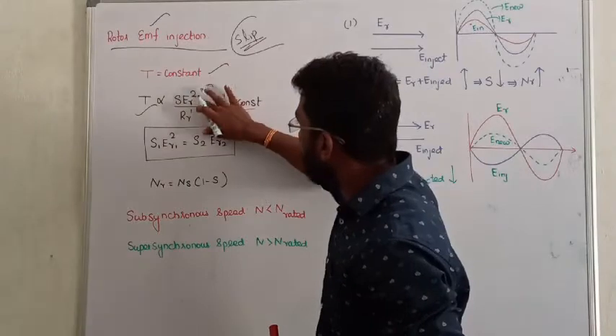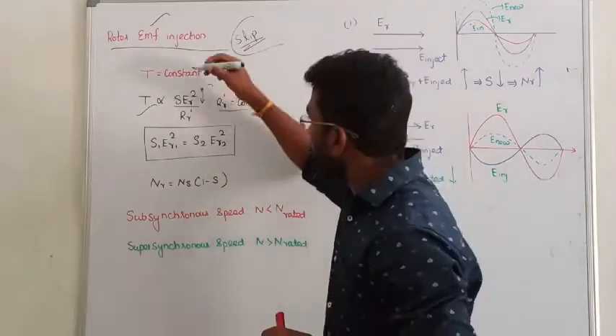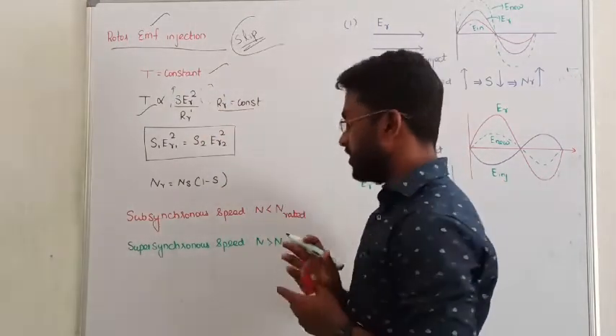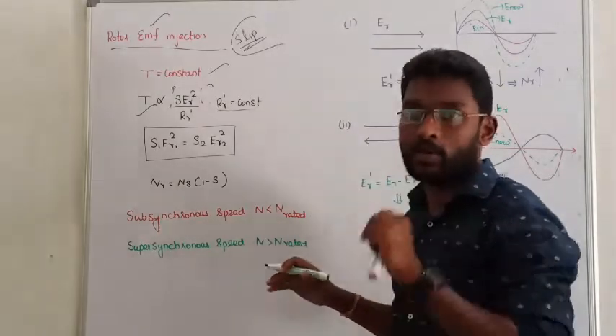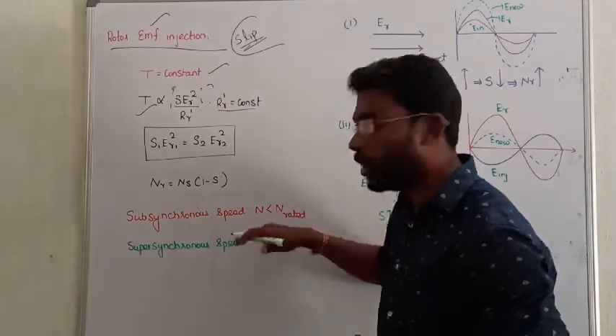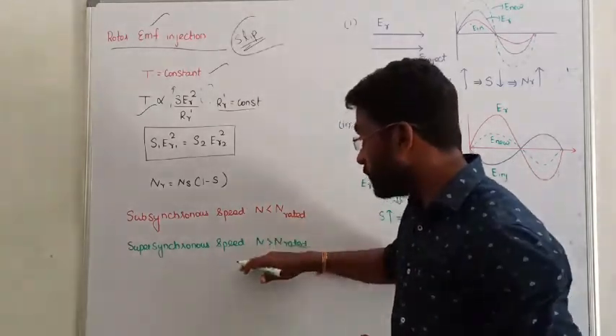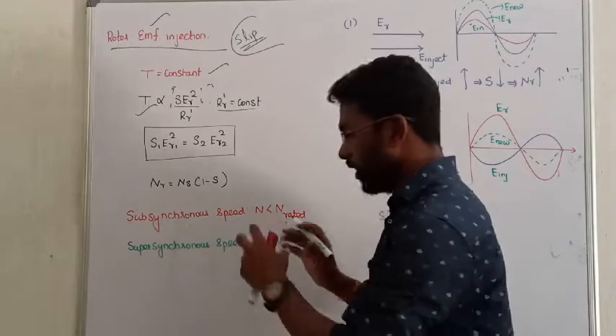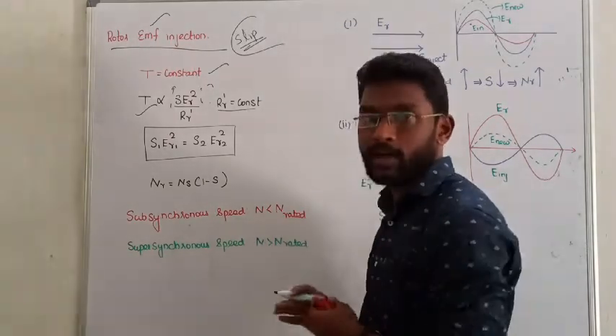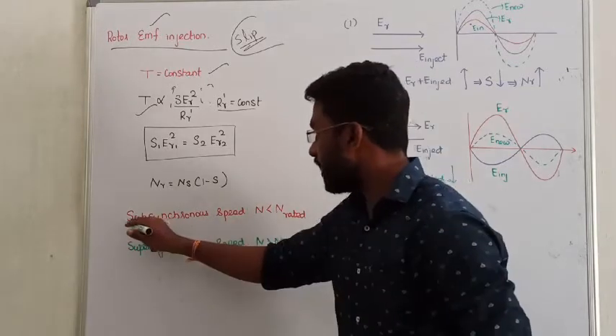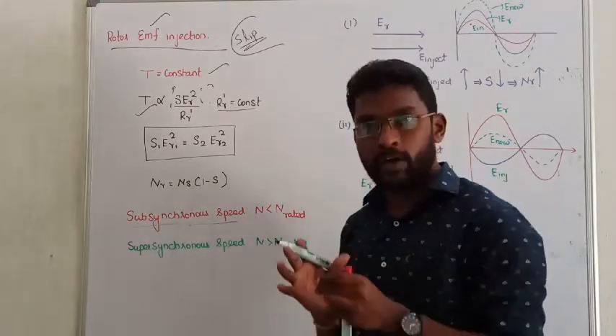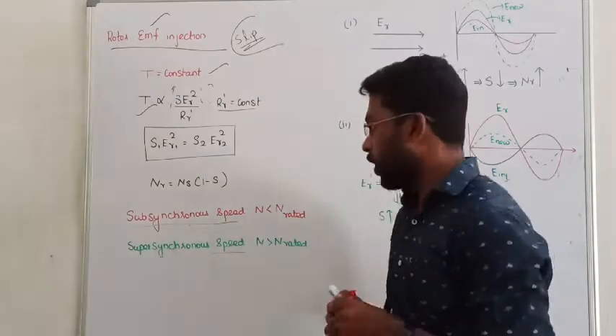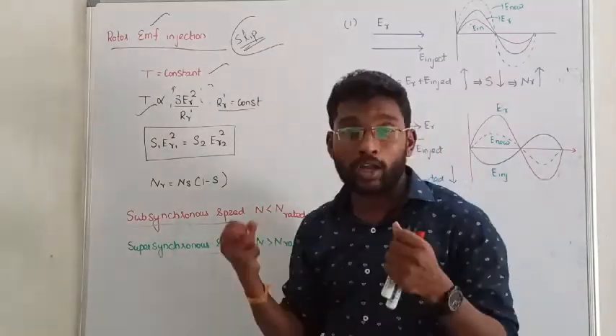Suppose if we reduce the injected voltage — that is, the rotor voltage — then the slip value will increase. There are two cases, which is the biggest advantage of the Rotor EMF Injection Method: we can maintain two types of speed control. Case one is below rated speed control, and case two is above rated speed control. Below rated speed is called sub-synchronous speed; above rated speed is called super-synchronous speed.